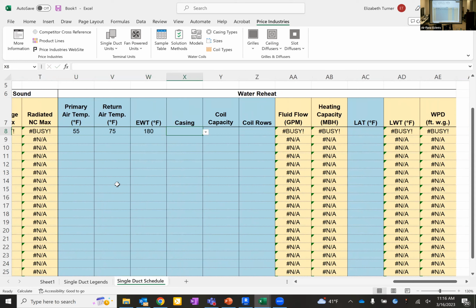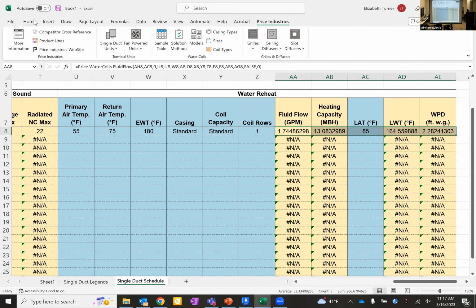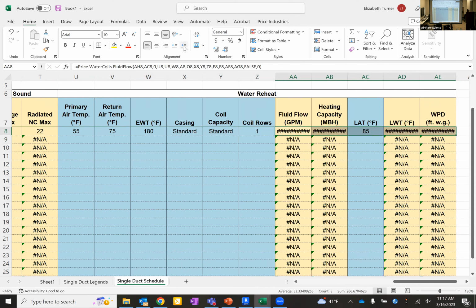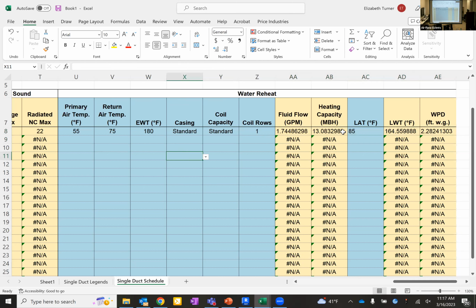Entering water, start with 180. Standard casing, standard coil. We talked about oversized casings earlier. You can look at performance in here with that. Start with one row and try to target a leaving air temperature of 85 degrees. So here pretty quickly, I've got all of my performance already calculated in a schedule view. I'm sure you all are not specifying to 8 significant figures. We are working on an update to get this brought down to more reasonable numbers. I'll just leave it for now.